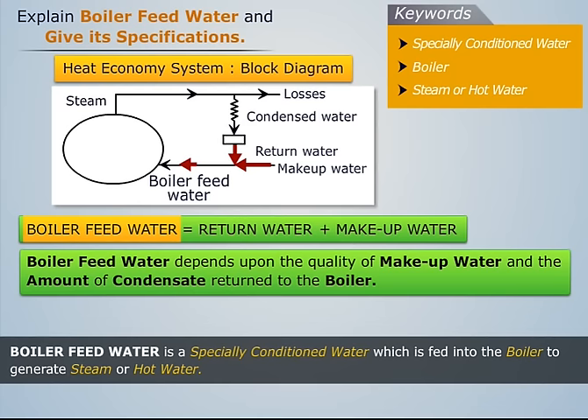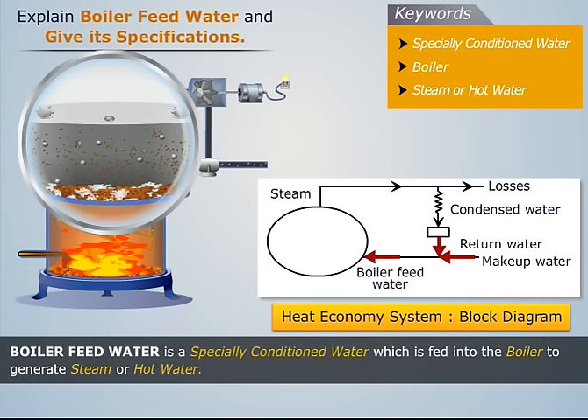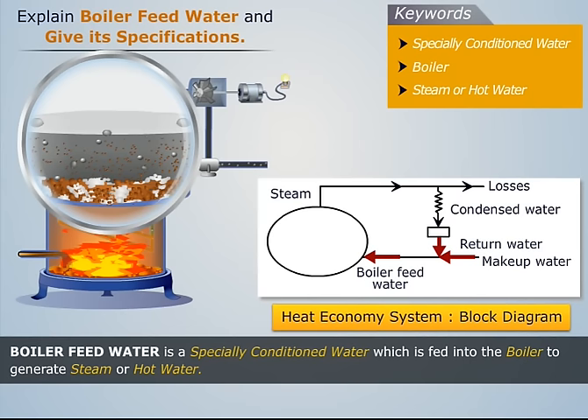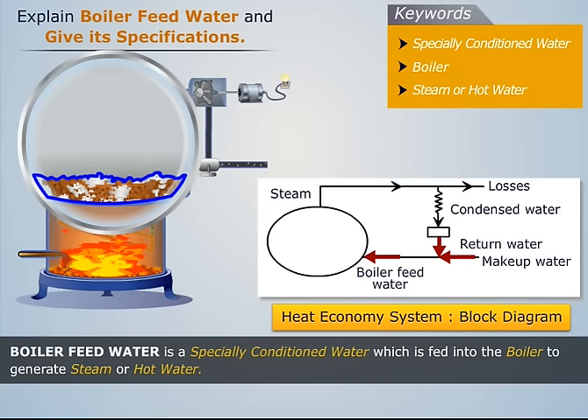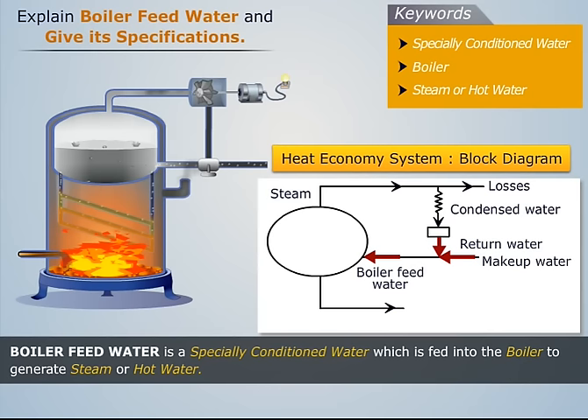Sometimes impurities settle down at the bottom of the boiler after steam is produced. Steam which escapes from the boiler normally contains liquid droplets and gases, so the remaining water at the bottom may pick up all the foreign matter from the water that was converted to steam. This results in the accumulation of impurities at the bottom of the boiler. These impurities can be removed by discharging some water from the boiler to the drain — a process called the blow-down operation.